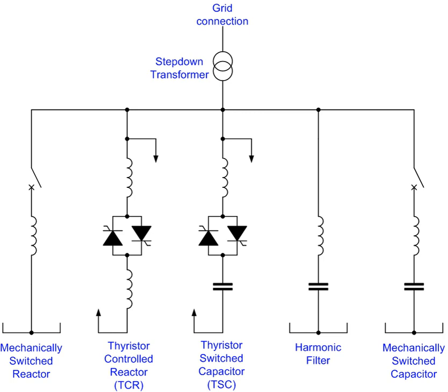the reactor may be variably switched into the circuit and so provide a continuously variable VAR injection or absorption to the electrical network. In this configuration, coarse voltage control is provided by the capacitors, and the thyristor-controlled reactor is to provide smooth control. Smoother control and more flexibility can be provided with thyristor-controlled capacitor switching. The thyristors are electronically controlled.